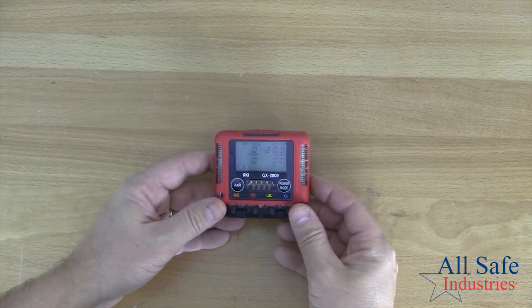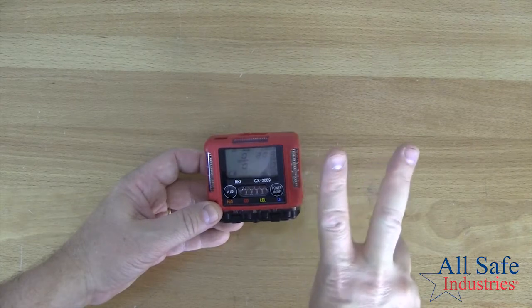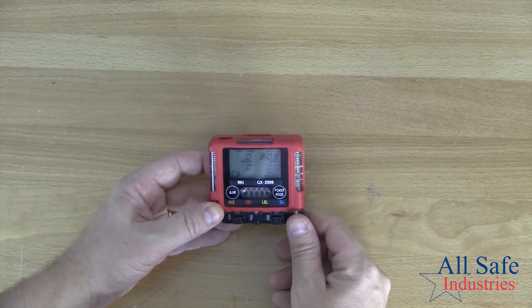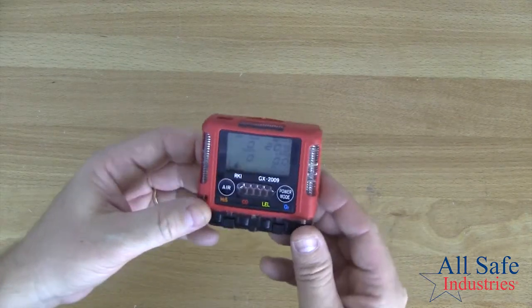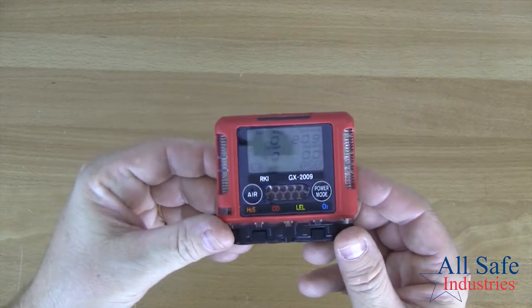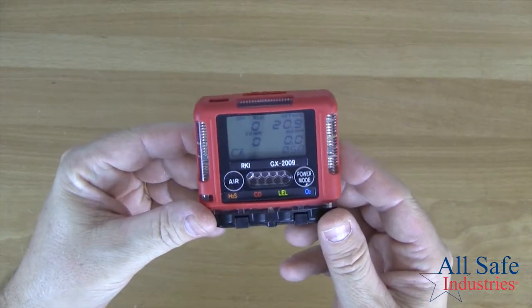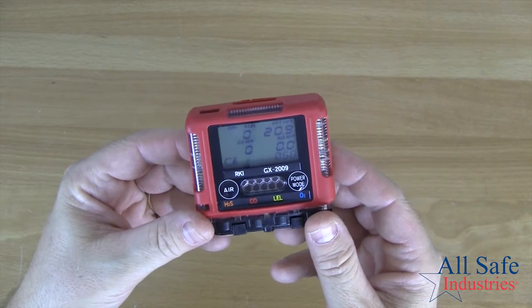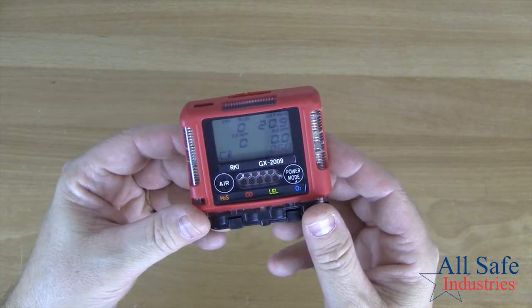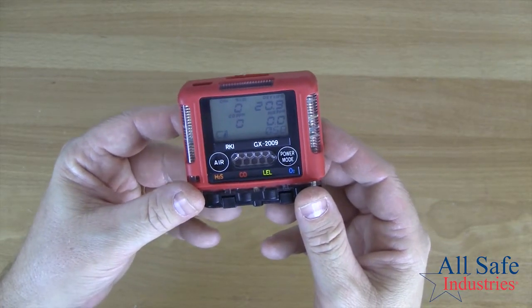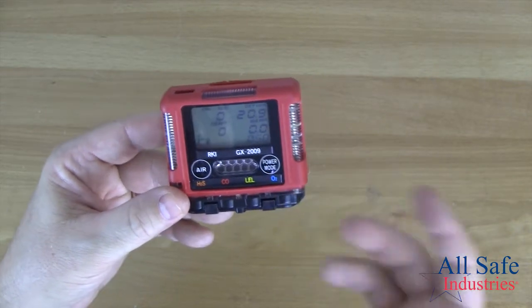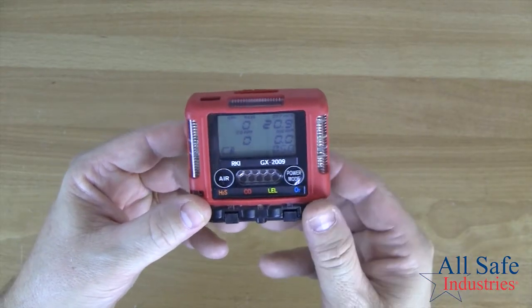Alright, so once the meter's turned on and warmed up, there's two steps that you're going to want to follow before you start using the meter. The first is going to be a fresh air calibration. So the fresh air calibration couldn't be easier. The most important thing there is just to make sure that you are in fresh air. If you have a background of a flammable gas or a toxic gas, obviously you could throw the readings off on your meter. So you want to make sure that you're in fresh air. And then it couldn't be easier.